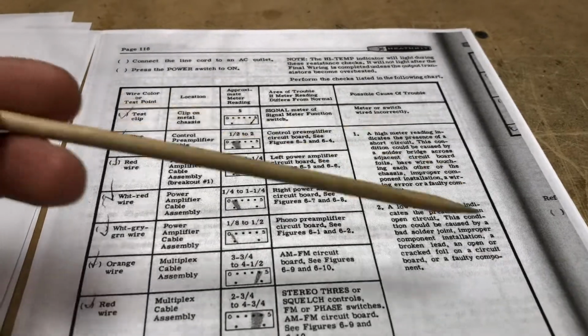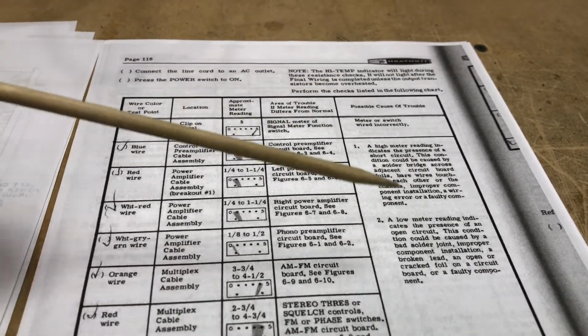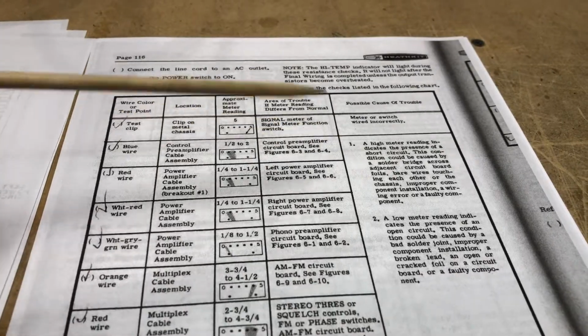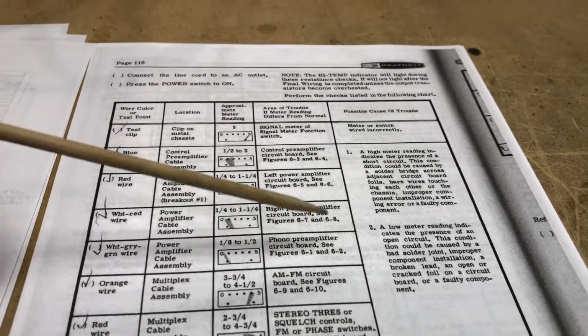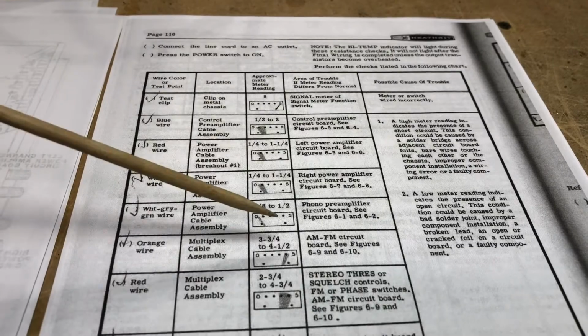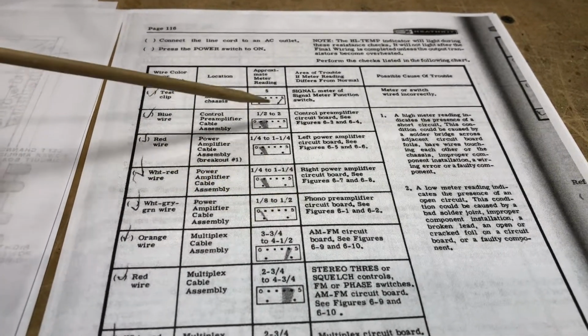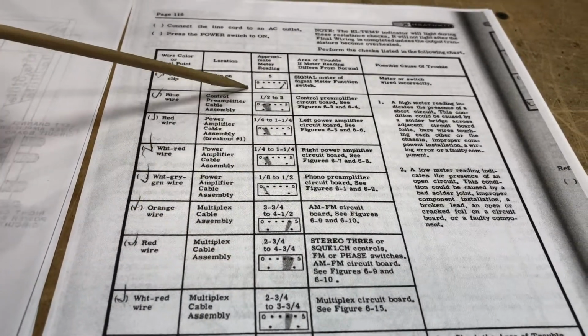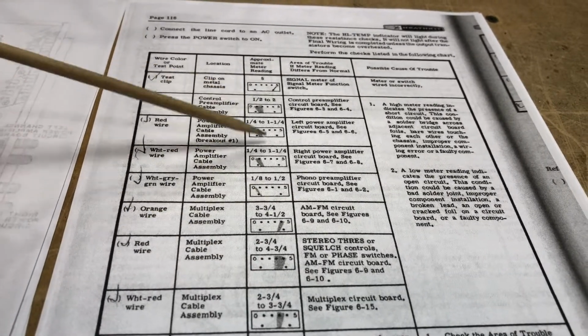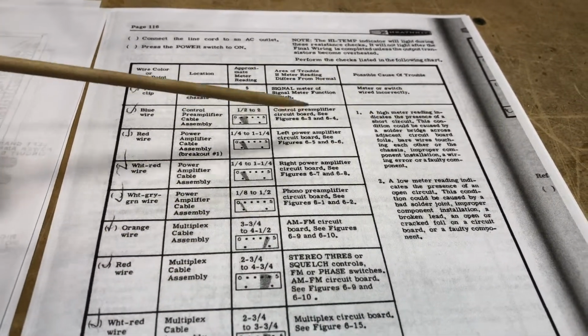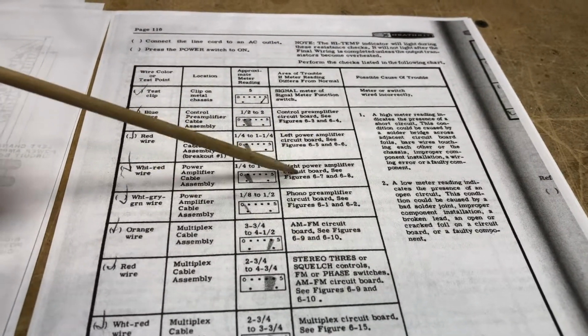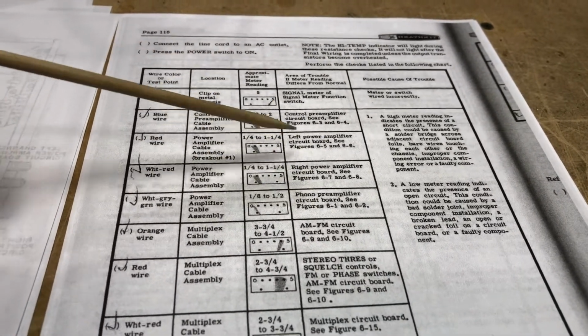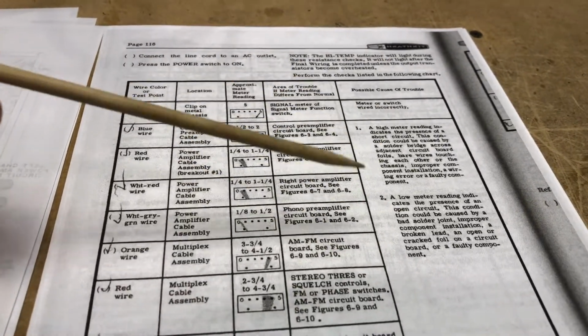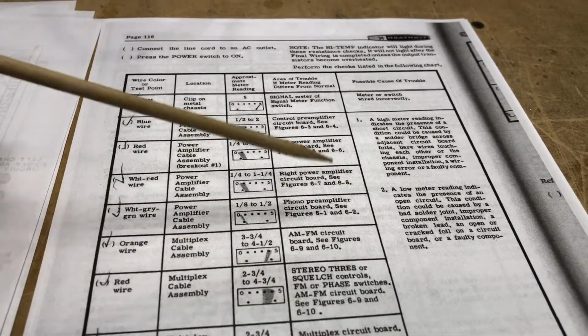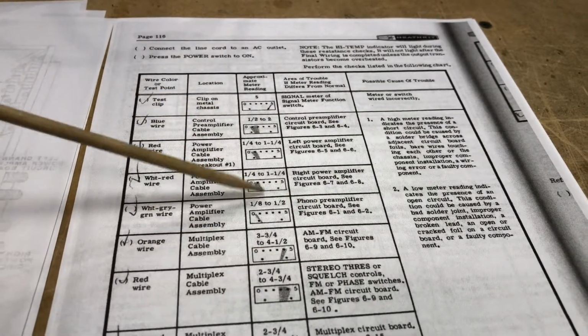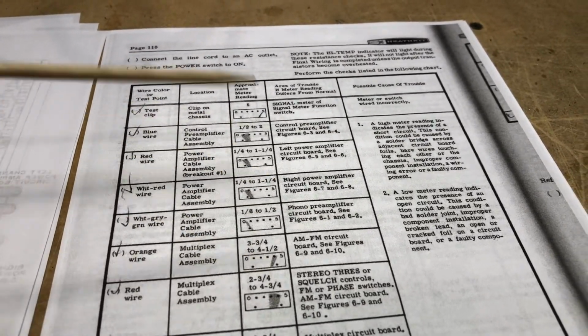Nowadays everybody doing this has ohmmeters, voltmeters, and dBm meters, but the procedure doesn't really specify what a correct resistance value is. So for this portion I'm just going to do the section that does tell you what the meter should indicate. When we do the voltage checks, I'll probably skip using the signal meter and just check the voltages with a voltmeter, comparing against the schematic for proper values. But we'll work through this part first, then go from there.